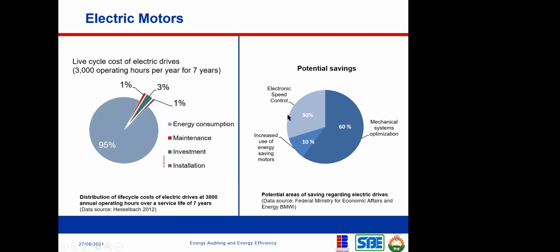Now, 30% can be done using electronic speed control. This is where VSD, variable frequency drive, comes into play. If your motor is oversized, instead of changing it entirely, you can actually deploy a VSD to tune it down so that it can match the load that it is carrying. So that's where VSD comes into play.